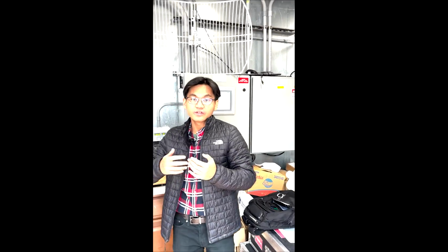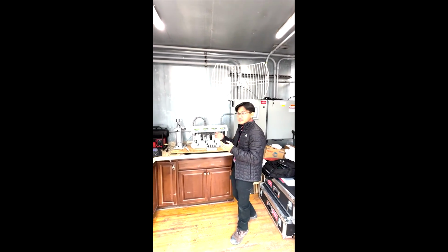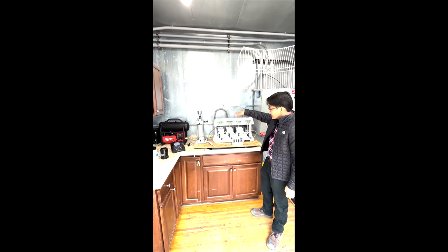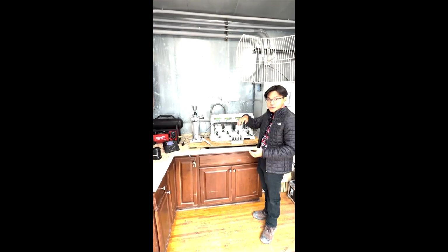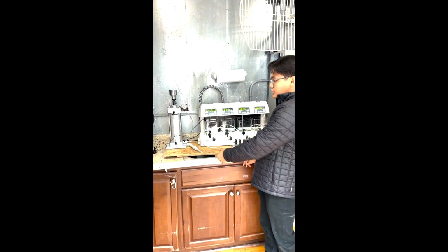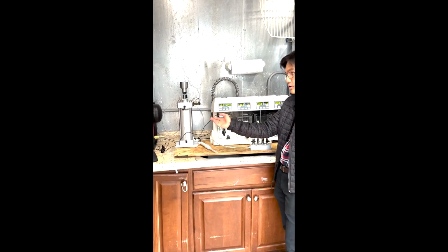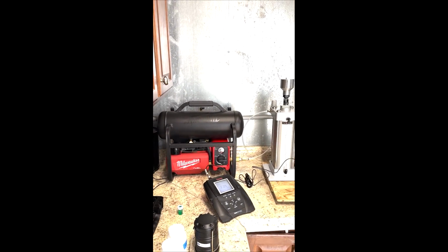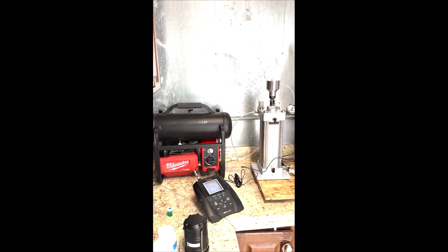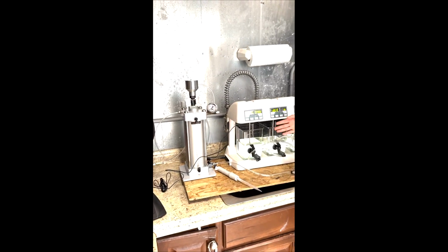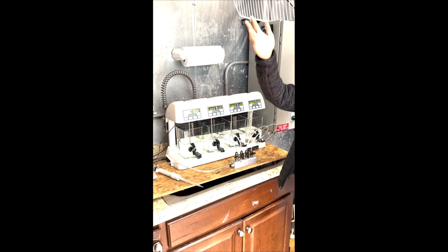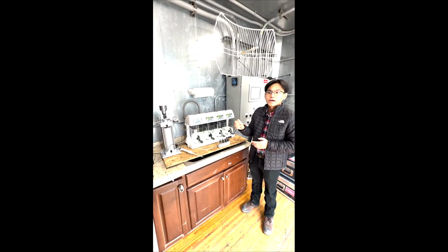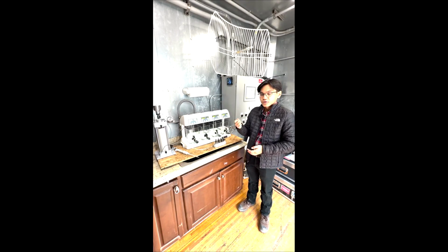And what we've also started to do on site is do some simulated tests. So what I just showed over there was the full-scale DAF, and this is a jar tester that allows us to simulate the DAF process. So over here, I have an air compressor that's feeding air into here, excuse me. And then this device allows us to pipe air into each of these jars so that we can simulate the full-scale system at a smaller scale, so that we can really nail down how much chemical we need and some of the other fine things.